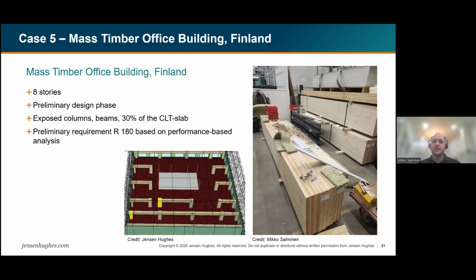But in this case, there were many reasons why some more detailed and advanced analyses were used. Compartmentation, for example, and also that the client and architect wanted to have some exposed timber surface: the columns and beams fully, and also around 30% of the CLT slab. So that, of course, increases the fire load when it's not encapsulated. And that's something we need to take into account in our analysis. The figure in the middle is a fire simulation model of one floor, where we are able to take the timber surface into account when it ignites. So it, of course, increases the heat release rate and fire load in the compartment, but it needs to be taken into account.